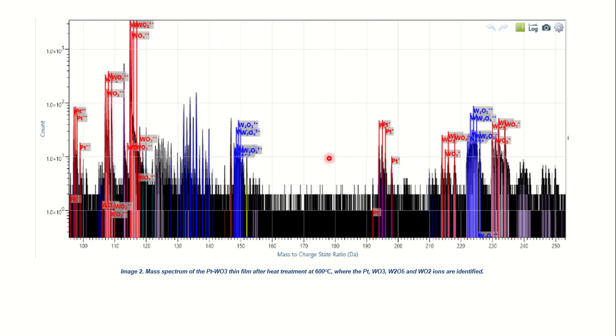The mass spectrum is the first step for the analysis because it allows us to identify the chemical elements and their ions that travel to the detector from the sample according to the atomic mass of each element and its time of flight, which is the time it takes the ion to move from the sample to the detector. Every ion is under the same electric field, which allows the acceleration of these ions to be plucked from the sample to the detector.